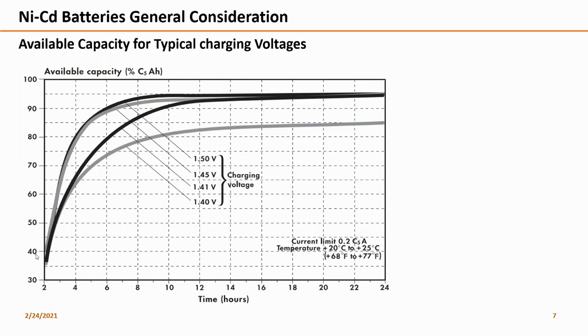Even with nickel cadmium batteries - generally in lead acid we used to measure the density of electrolyte - but in nickel cadmium it's not required to measure the density at all, because based on temperature and operating parameters, the density varies a lot. So we will not be identifying anything based on density. In lead acid, we identify the density and check for electrolyte top-up, or further consideration on it. But with nickel cadmium, that is not there.